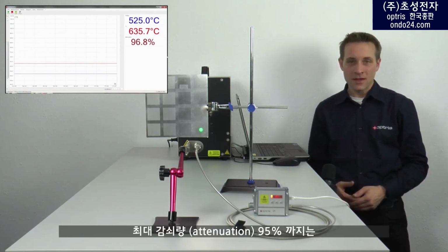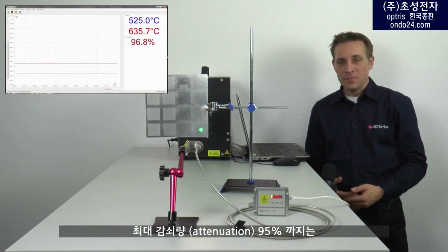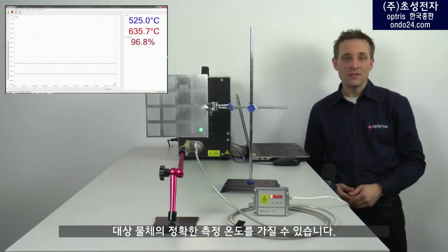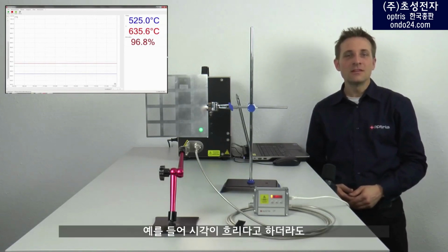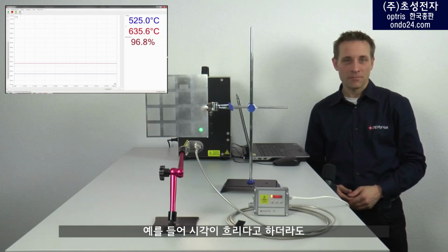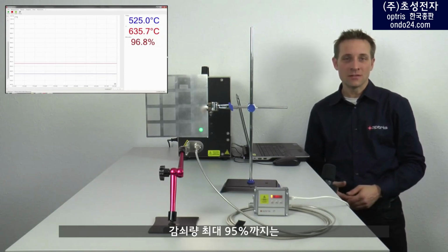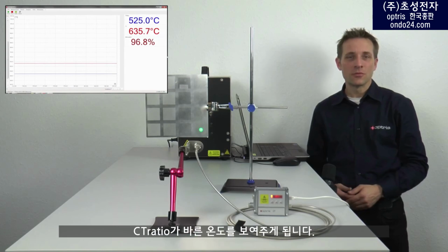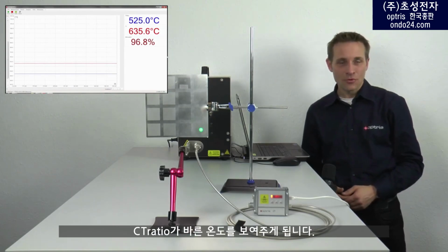Up to an attenuation of 95%, we have the possibility to present the correct object temperature. For example, even in poor visibility conditions, with an attenuation of up to 95%, our CT ratio still shows the right temperature.